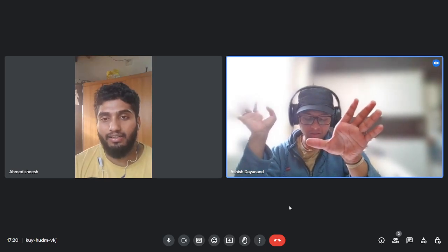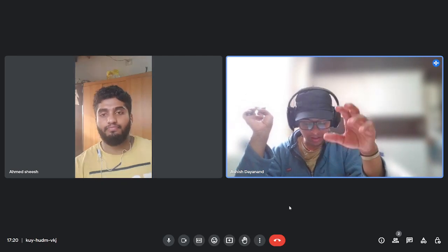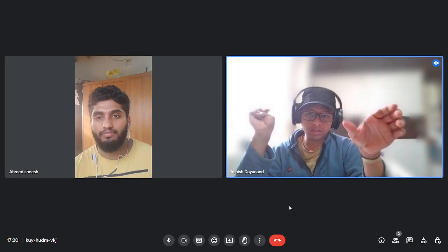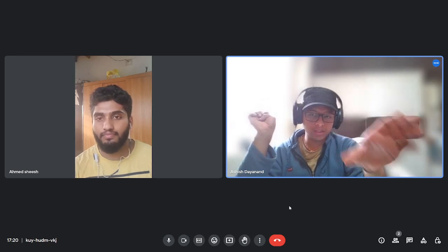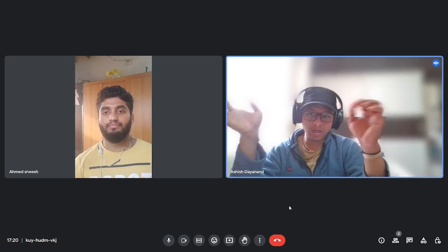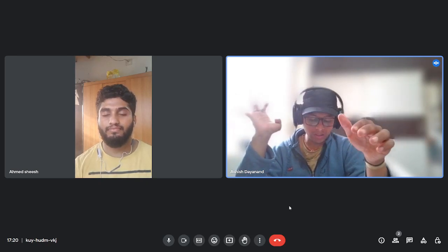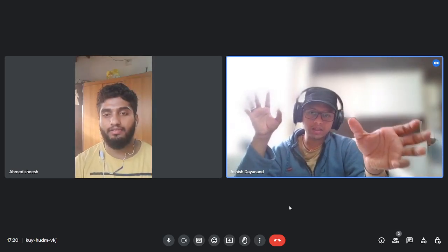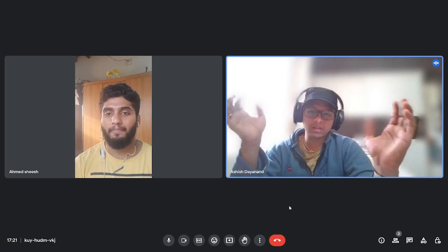First, there will be a pulser. The high frequency sound wave is sent through the pulser. In the pulser, a high voltage electrical pulse enters into the transducer. Then the transducer sends high frequency ultrasonic sound energy which hits the discontinuity, wherever the crack is. Then part of the sound is reflected back and enters into the transducer. Then the reflected sound waves are converted back into an electrical signal. Then the electrical signal is displayed on the display unit or a receiver. So like this you have to tell each and everything perfectly.